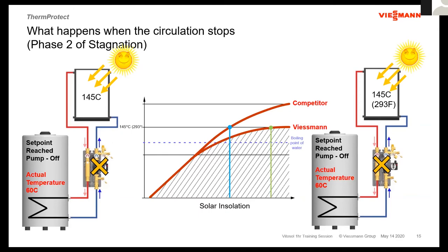And again, looking at that time difference now, it's because the emittance of radiation is actually increasing as the collectors heat up here. You can see that that time is even longer as far as the difference from getting from one point to our collector getting to that same set point. Again, more time for the system to correct itself without getting into a situation where we have to stop this front pump from coming on physically because the collectors are getting too high as far as their level of temperature, and we don't want to damage the components.